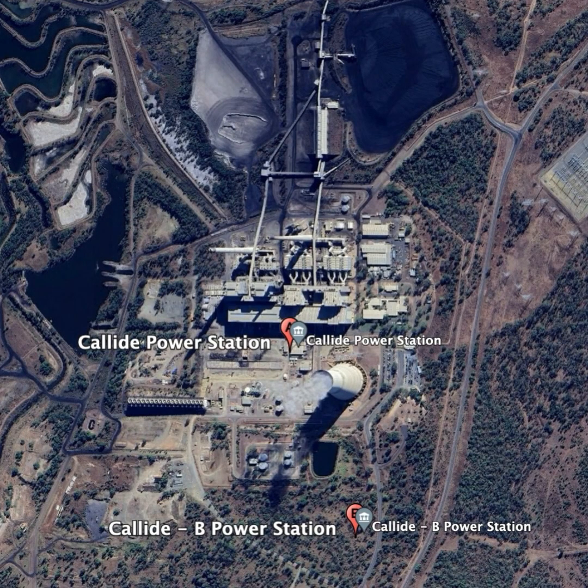On Monday, the 24th of May 2021, at 2:08 p.m. local time, Unit C4's DC battery charger was energized and connected directly to its battery string in offline charging mode to ensure the batteries were at a maximum state of charge ahead of the following day's planned work to switch over the new battery charger to fully online operation. By approximately 8 p.m. that evening, the battery string in Unit C4 was indicating that it was fully charged.